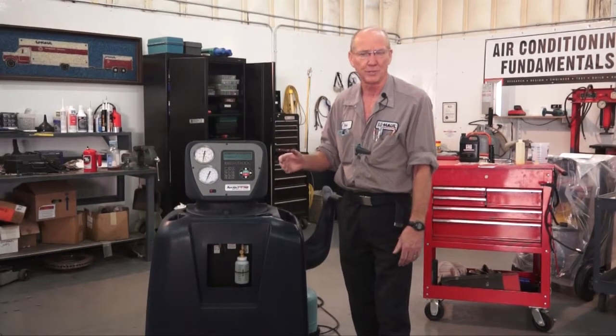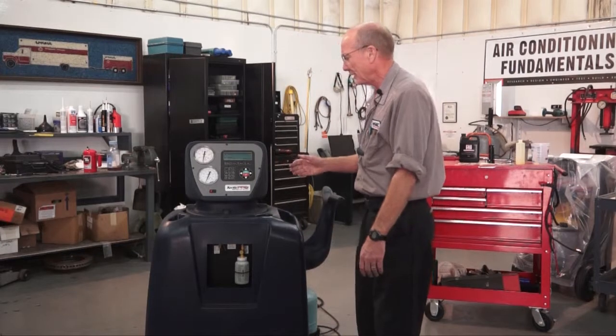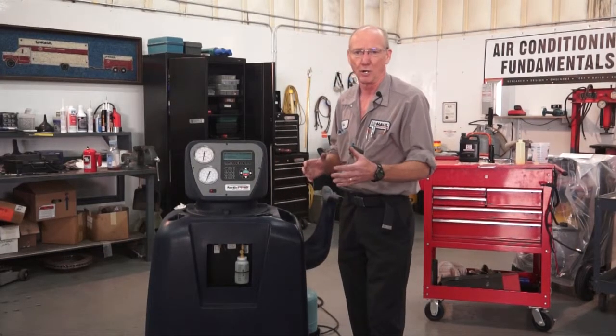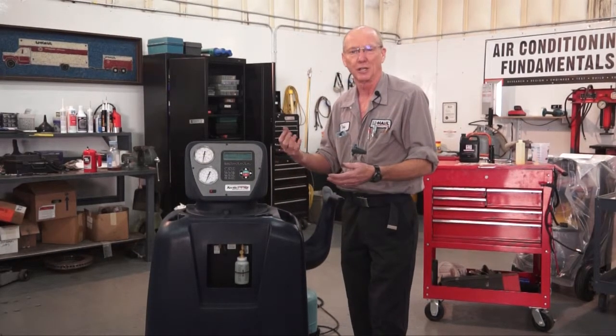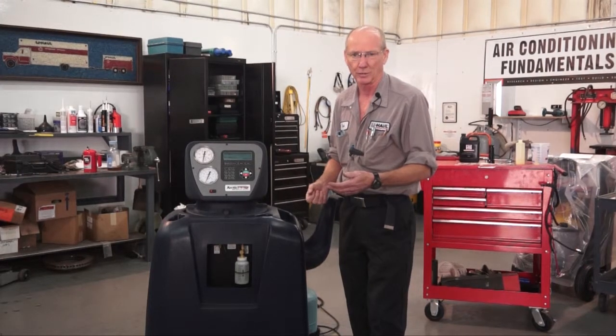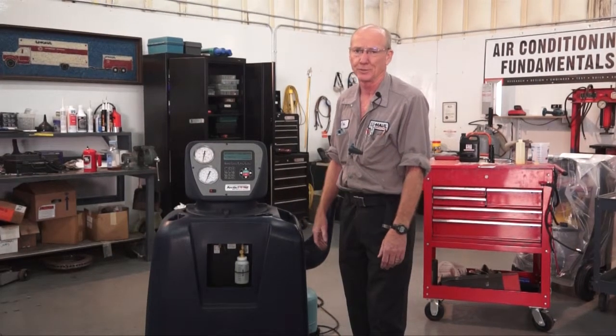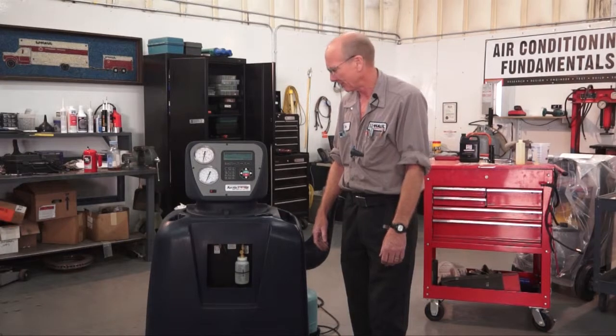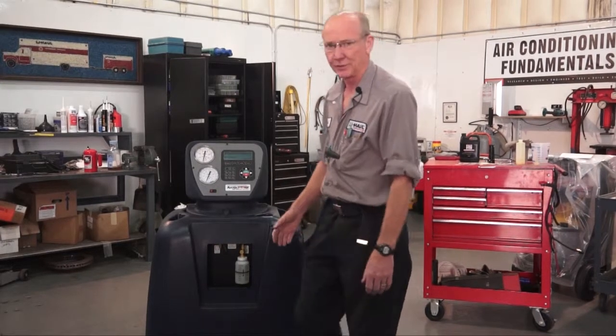It's always good to replace the vacuum pump oil when the vacuum pump is still warm. That way the oil's a lot thinner, you'll get a lot more to drain out, and it'll drain out quicker, because it's a little time consuming to replace this vacuum pump oil. So I'm going to go ahead and do that.